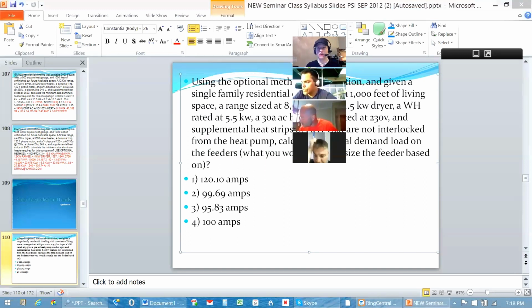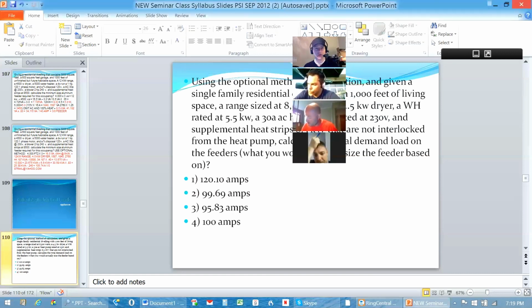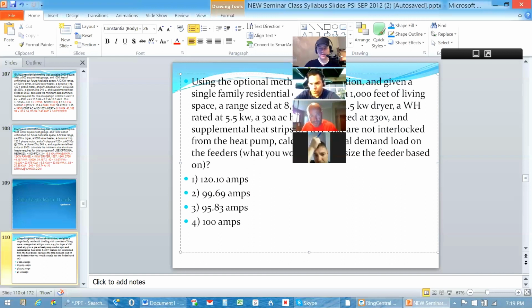The beginning of the earlier steps, the process is I'm going to take the square footage, which is 1,000 square feet in this case. So I'm looking at coming in here with 1,000 square feet times 3 volt-amps per square foot, which gives me 3,000. Then I have to add that 4,500 because I have that no matter what on these pre-required circuits there. So I'm going to add those two numbers together, and that's going to give me a total of 7,500 for those two.